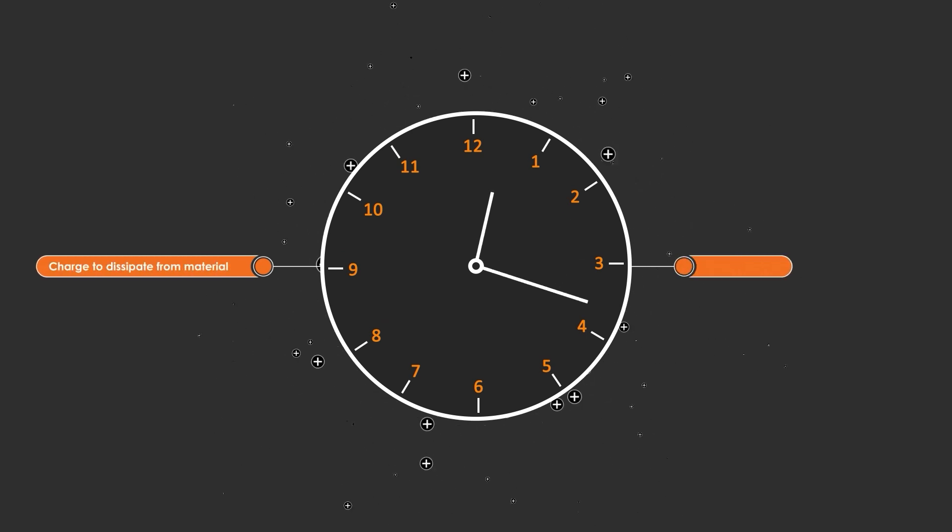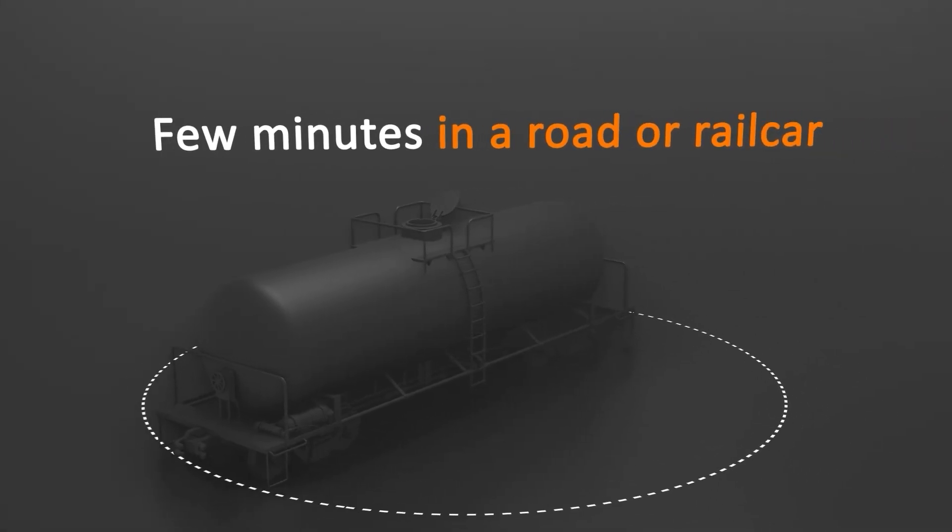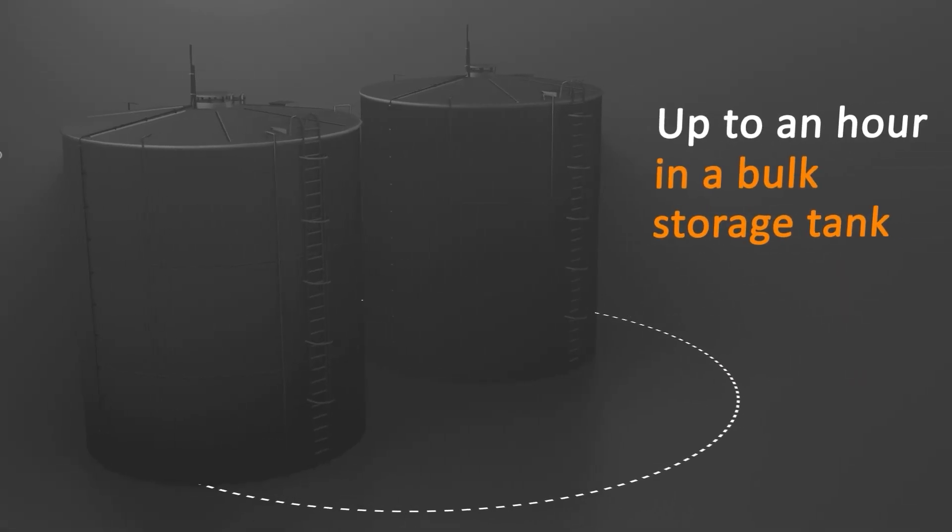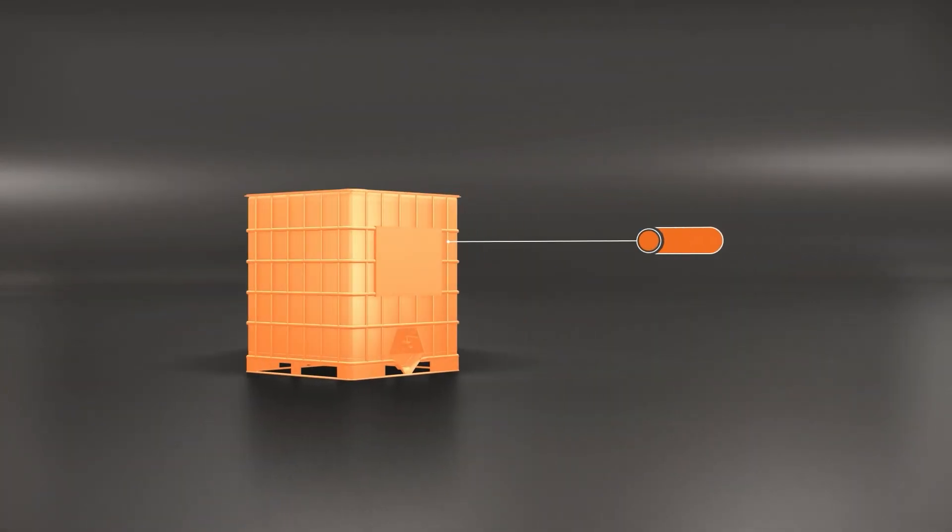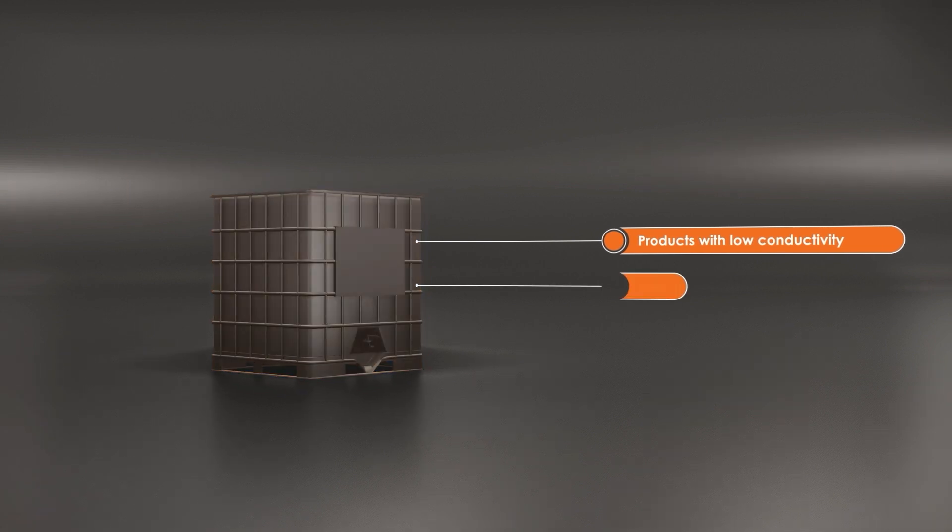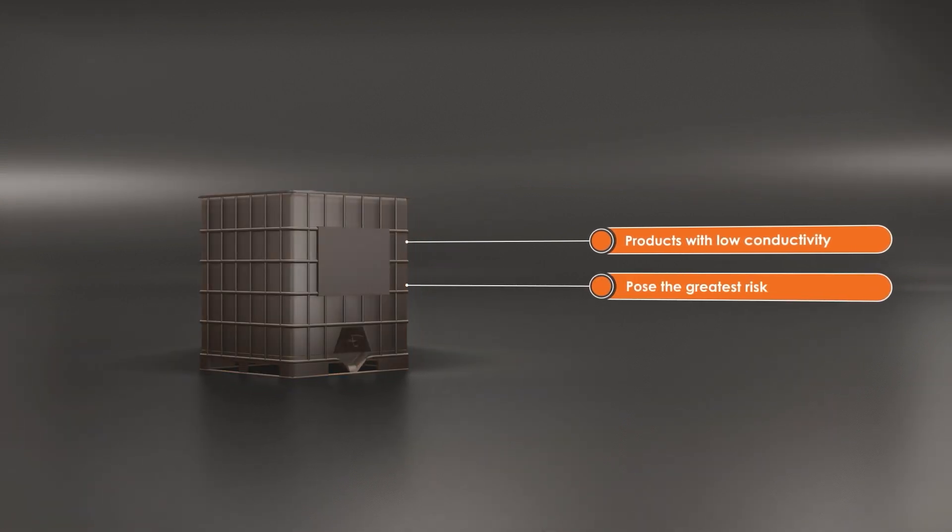The time taken for a charge to dissipate from a material, and hence the spark hazard to be eliminated, is called the relaxation time. This time can range from a few minutes in a road or rail car and up to an hour in a bulk storage tank. Products with low conductivity and hence the ability to retain an electrical charge pose the greatest risk.